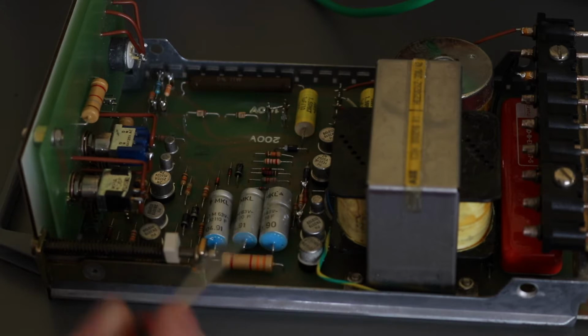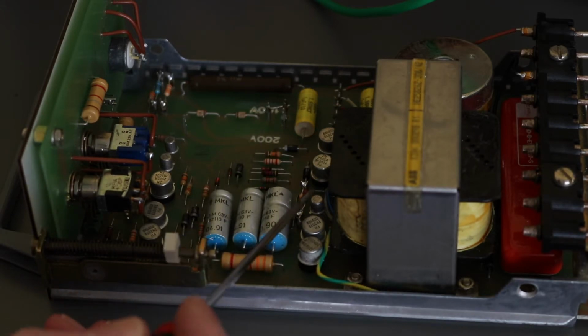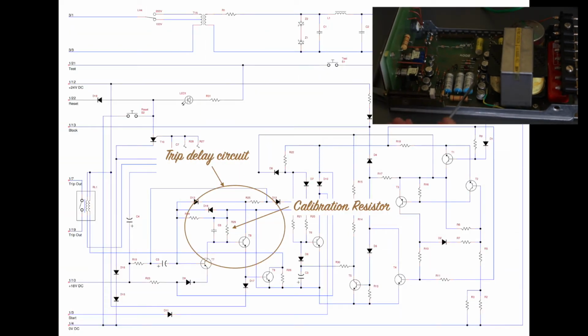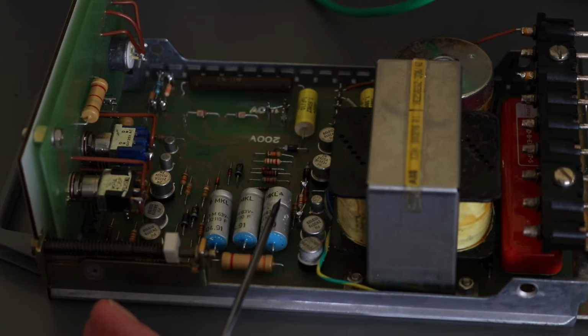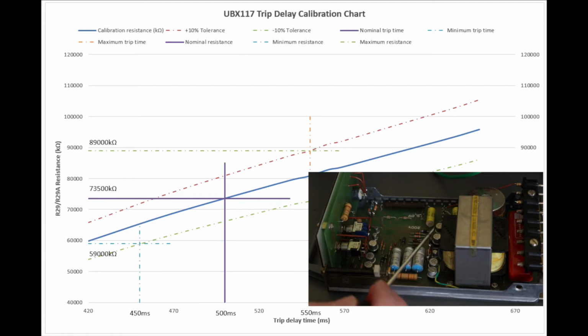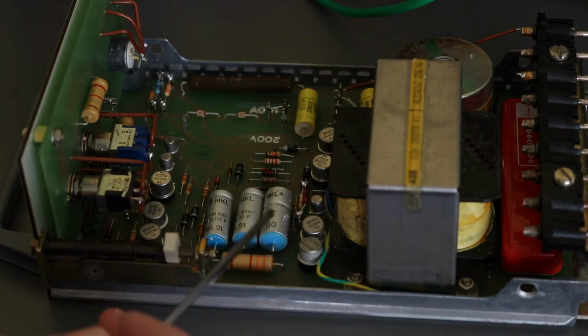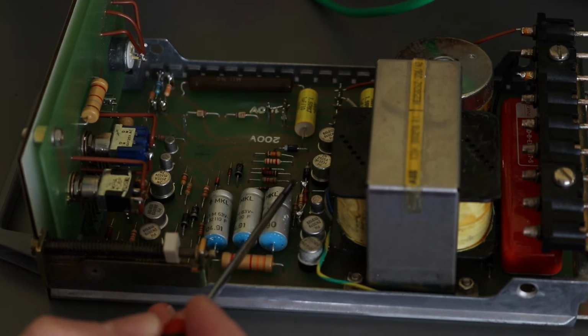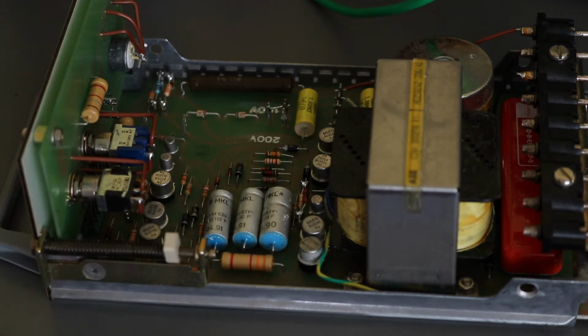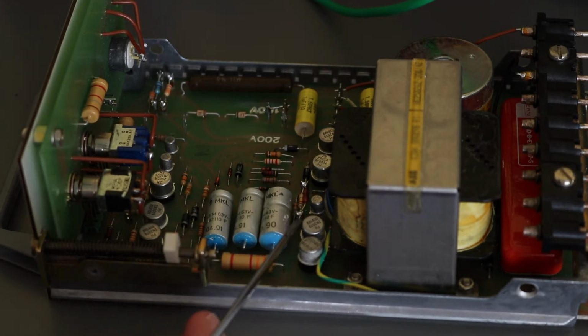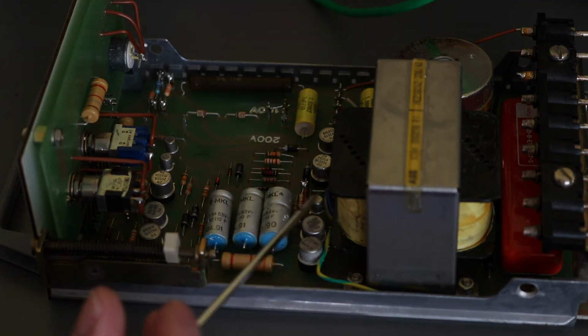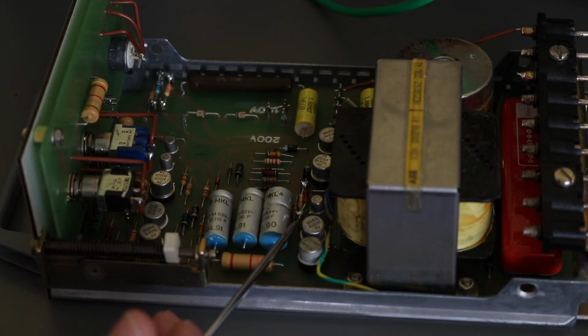So once I've replaced all those capacitors, to calibrate the timing is this pair of resistors here that are in parallel with another resistor just underneath this capacitor. I have a calibration plot from previous relays that I've repaired with this, so I can plot the original timing of around about 670 milliseconds for this particular relay, see where that sits on my plot in relation to the value of these resistors, and calculate through to find the correct resistors to get me down closer to the 500 milliseconds. For the timing I'll take a plus or minus 10% deviation from the nominal 500 milliseconds, so I'm looking for between 450 and 550 milliseconds.